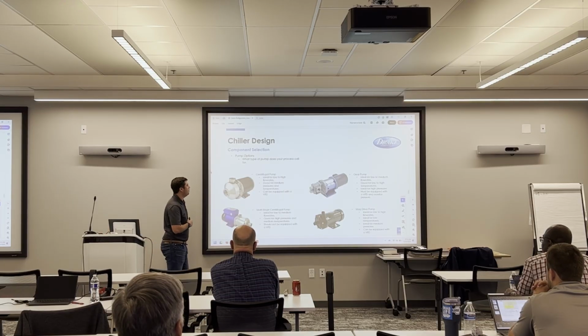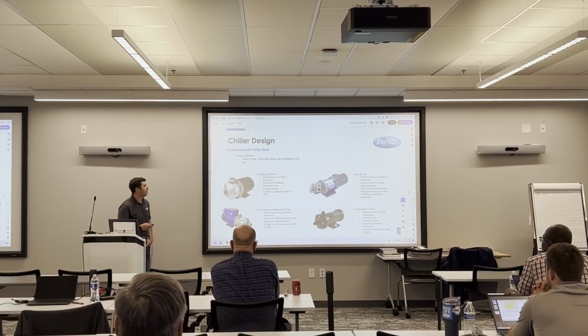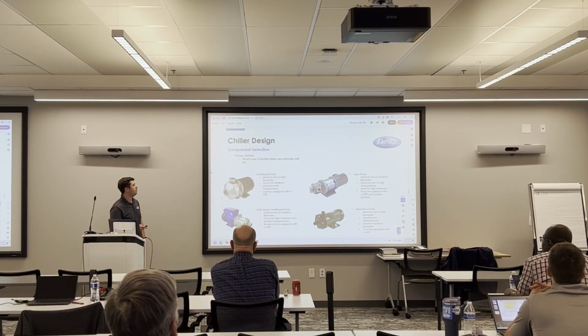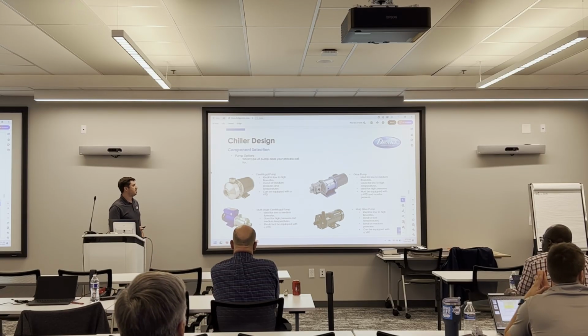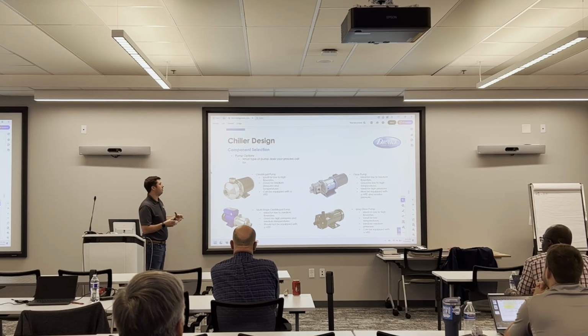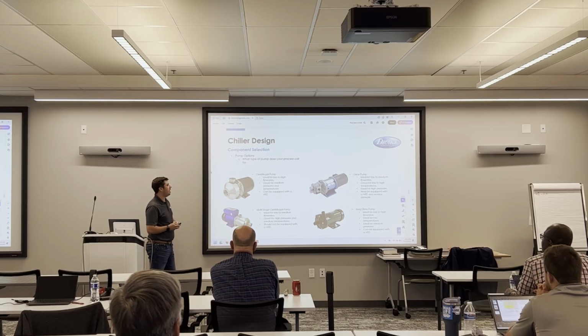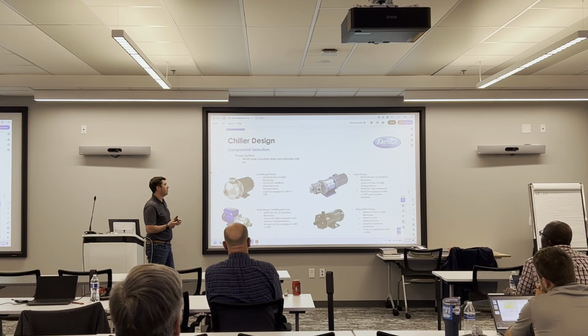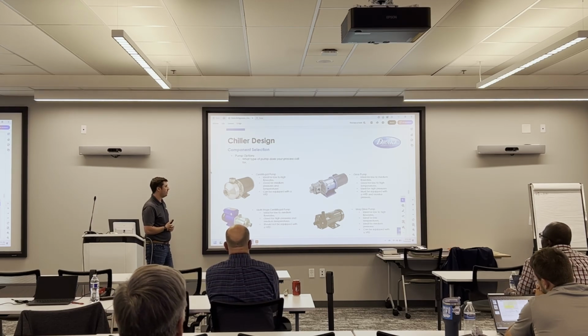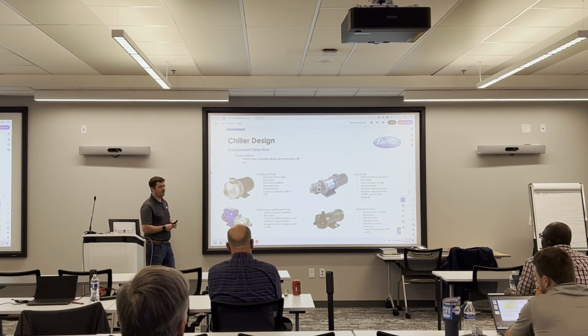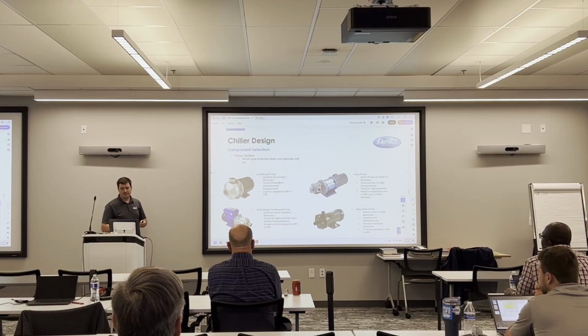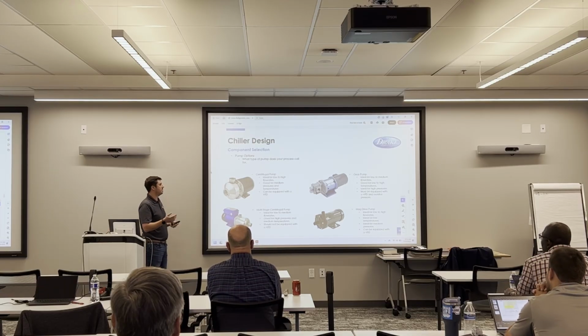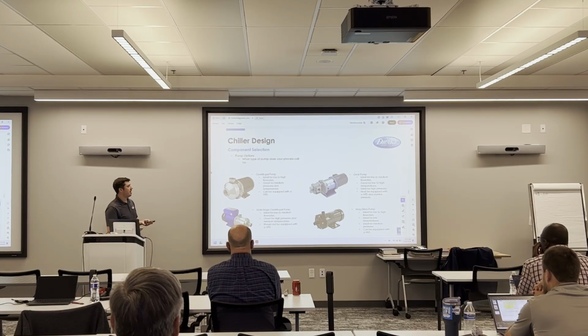So, some different types of pumps that we see in our industry. The ones we use primarily are centrifugal style pumps. Just essentially a shafted motor with an impeller mounted onto it. Ideal for low to high flow rates. It's good for medium pressures, medium temperatures. When I say medium pressures, medium temperatures, I'm talking maybe 50 PSI, anywhere from 40 to 70 degrees. You can equip these pumps with VFDs if you need to modulate flow.